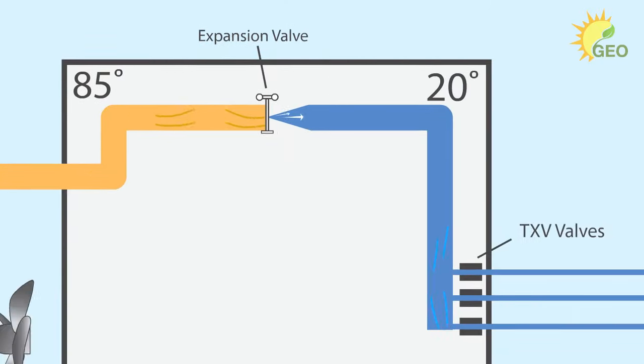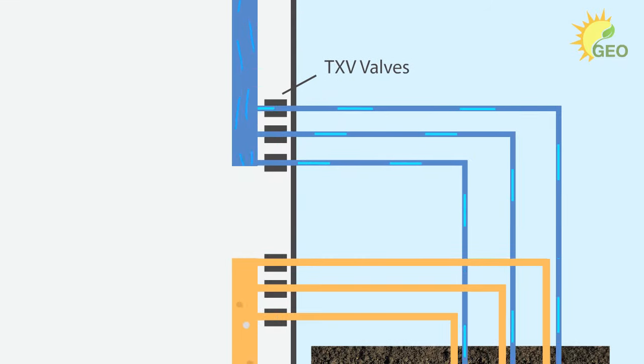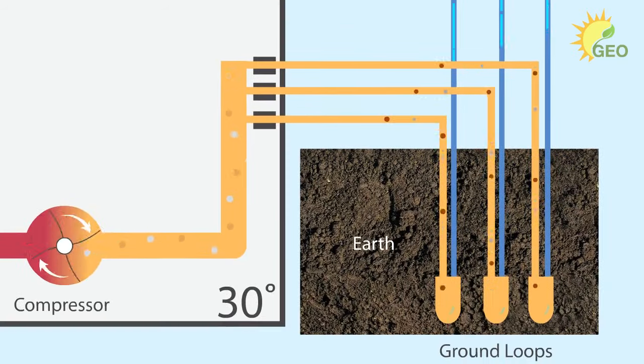The air blowing across this coil absorbs the heat energy and distributes it throughout the home. As the refrigerant leaves the coil, it condenses back to its liquid state and moves toward the expansion valve at 85 degrees. The expansion valve is basically like a dam with a small hole. When the refrigerant passes through the expansion valve, the pressure rapidly decreases and the temperature falls to 20 degrees.